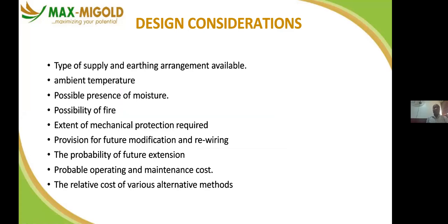So in electrical installation, you need to consider the following when designing. Type of supply and earthing arrangements. Earthing is very, very key in electrical installation. If your earthing is not properly done, that means you have not done anything. The lives of your personnel and the equipment are at stake. So you have to get it right. First, you need to consider the earthing arrangement of your installation.